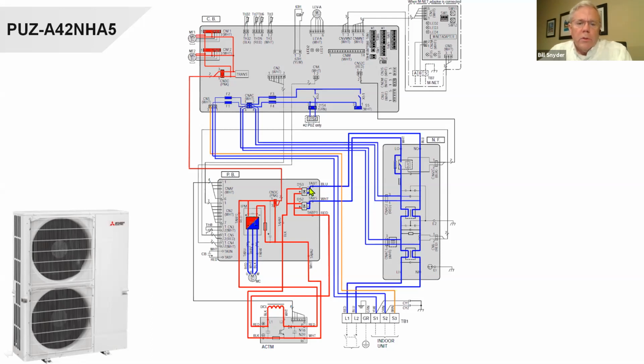You come through these 2 devices here, and it's converting the voltage into DC. So it's kind of like the intelligent power modules. You'll notice right here, the red wires, that's a DC, direct current voltage. It should be around 300 volts DC.